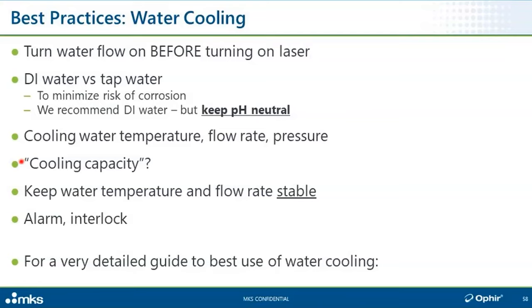But what we can tell you meanwhile is that, all things being equal, DI water, deionized water, which gets a bad rap sometimes, is in fact a recommended type of water to use in a closed cooling water system, subject to the condition that you keep the pH level neutral. And that's probably where the bad reputation comes in. So if you can check that, and there are ways of keeping the pH neutral, there are additives, there are methods of doing this, then we do recommend DI water. In many cases, city tap water works fine. Sometimes it doesn't. All right. And if that's of any concern, I warmly refer you to a white paper that we have on our website. I'm going to show you how to find it in a moment.